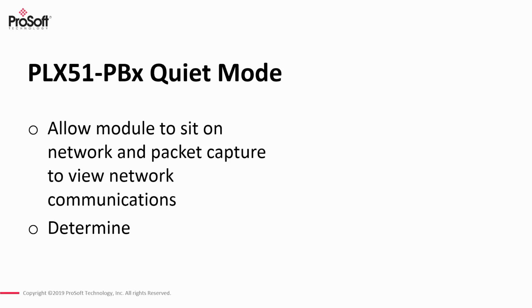Lastly, there's a third mode that you probably saw in one of my other slides, and it was the quiet mode. What quiet mode allows you to do is actually sit on the network and look at the communications on the network, utilize the packet capture and some of the different statistics, and determine what's going on on the network before actually actively participating as a device on the network. So all of the previous slides that show the event statistics, all the information on the PROFIBUS DP network, the packet capture utility, the live list, all of those are available in the quiet mode.